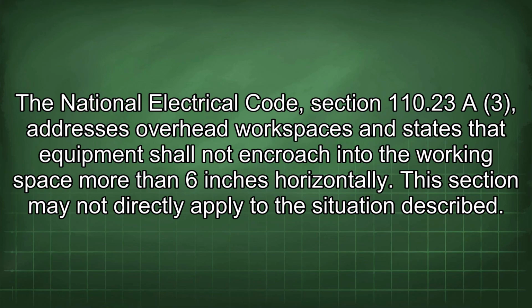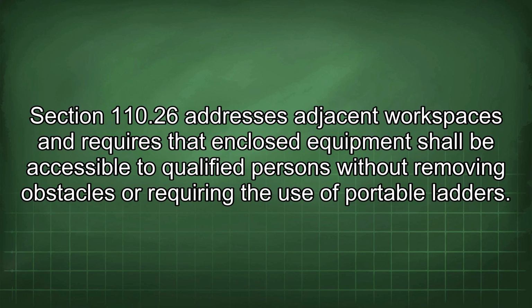National Electrical Code Section 110.23(A)(3) addresses overhead workspaces and states that equipment shall not encroach into the working space more than 6 inches horizontally. This section may not directly apply to the situation described. Section 110.26 addresses adjacent workspaces and requires that enclosed equipment shall be accessible to qualified persons without removing obstacles or requiring the use of portable ladders.